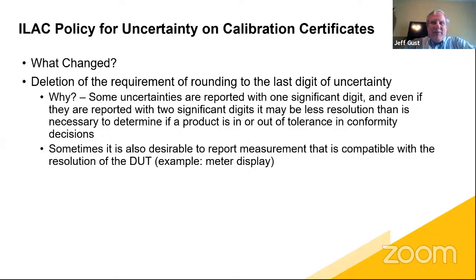So yeah, good question. Once again, I'm kind of surprised that we're still getting this many questions about BMC and CMC, because this was a solved issue in your accreditation if you're an accredited laboratory. And remember that we're talking about ILAC P14, so I'm making the assumption that everybody here is an accredited laboratory or wants to be an accredited laboratory. This has been assessed by your assessors using this for at least 10 years. So I don't think you have to worry about that. You can't use BMC. You've not been allowed to use BMC for at least 10 years. So, the point is, yes, you could never report an uncertainty less than your CMC.